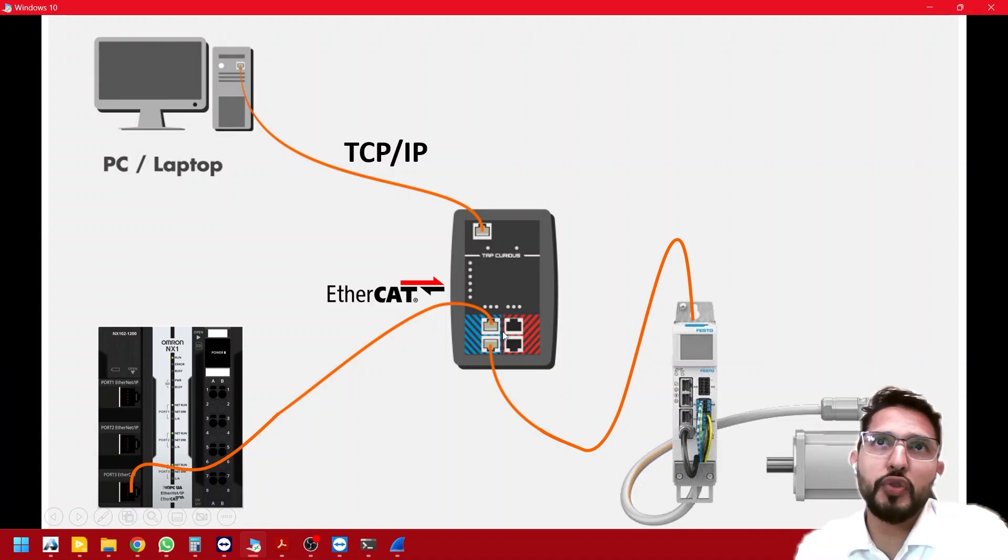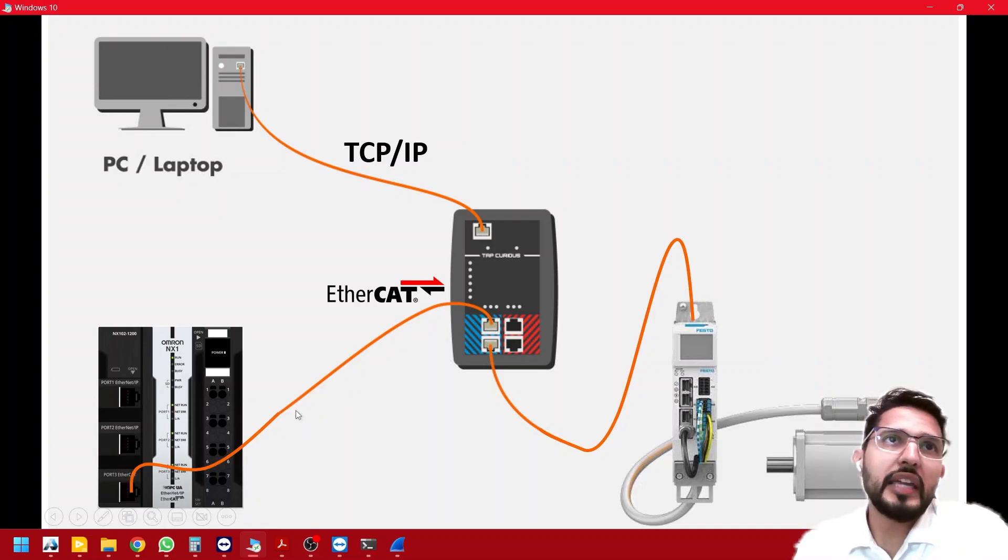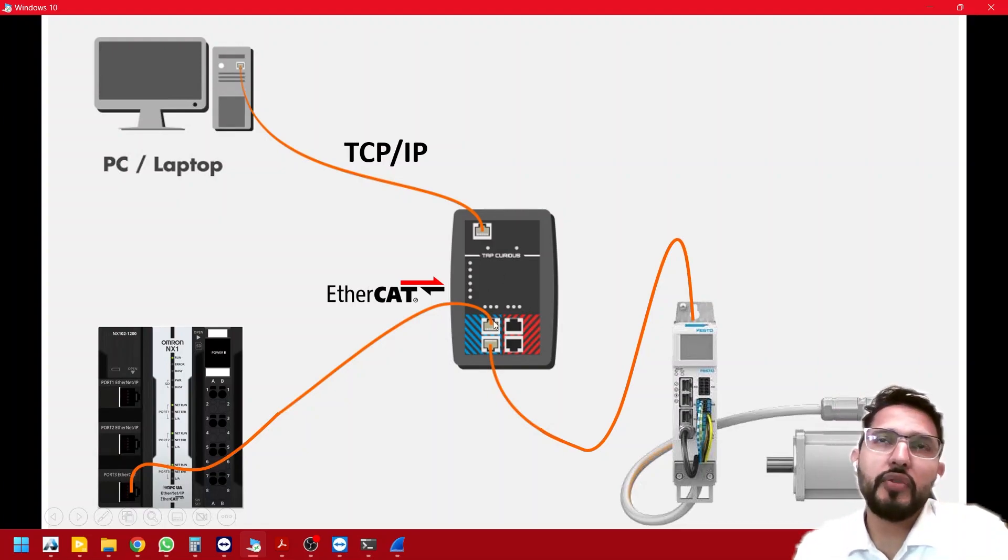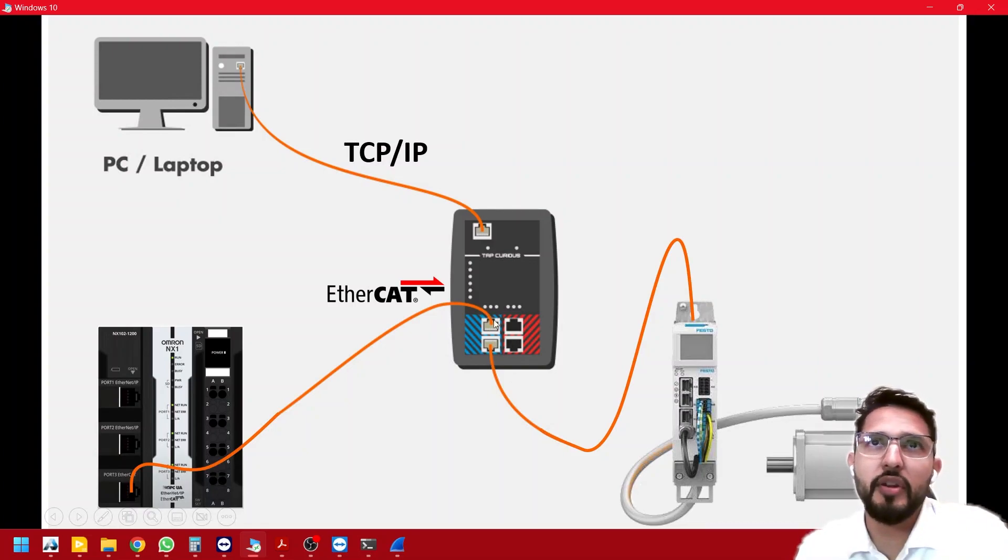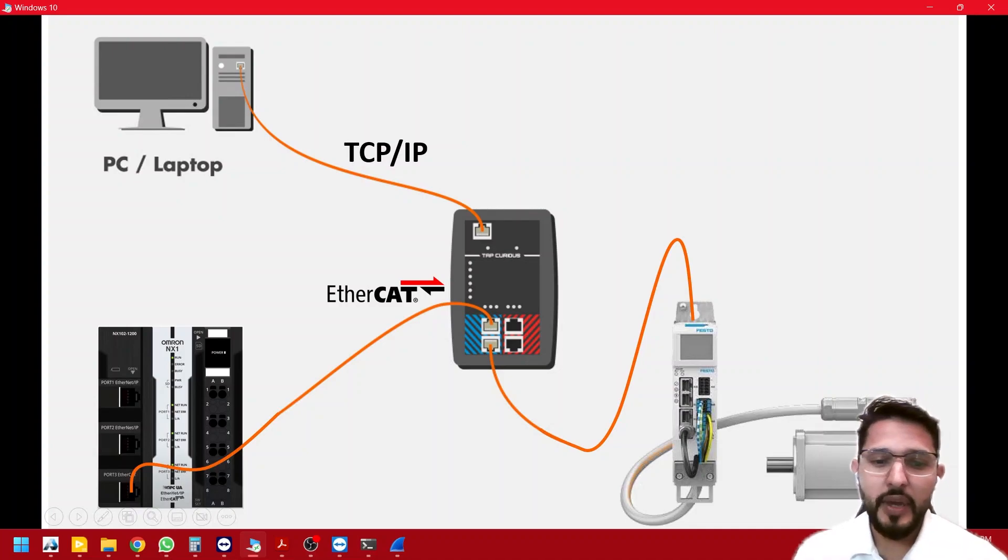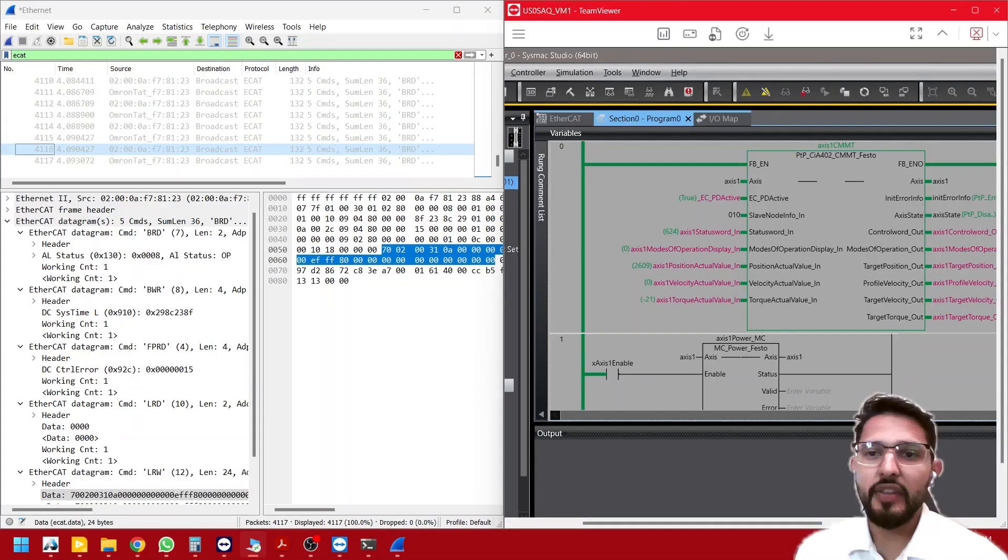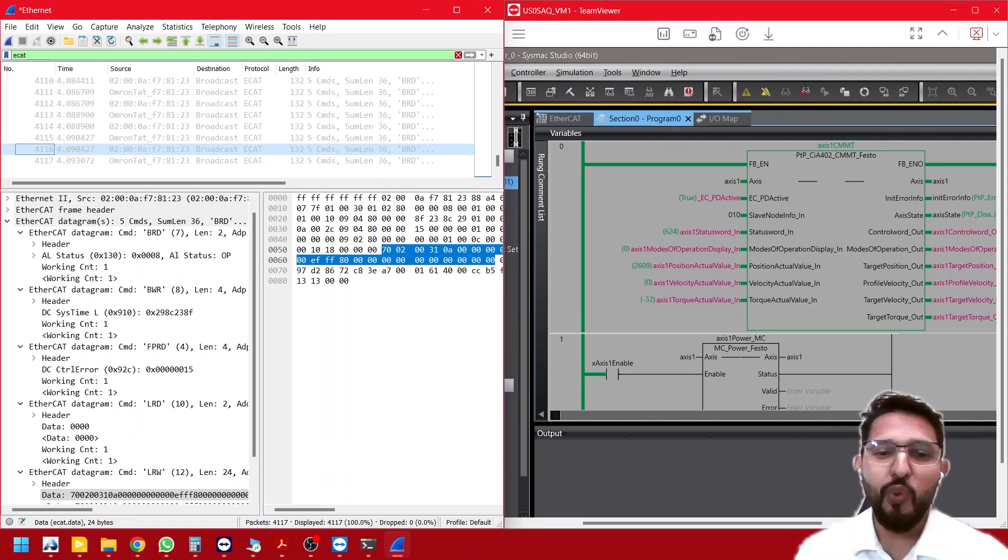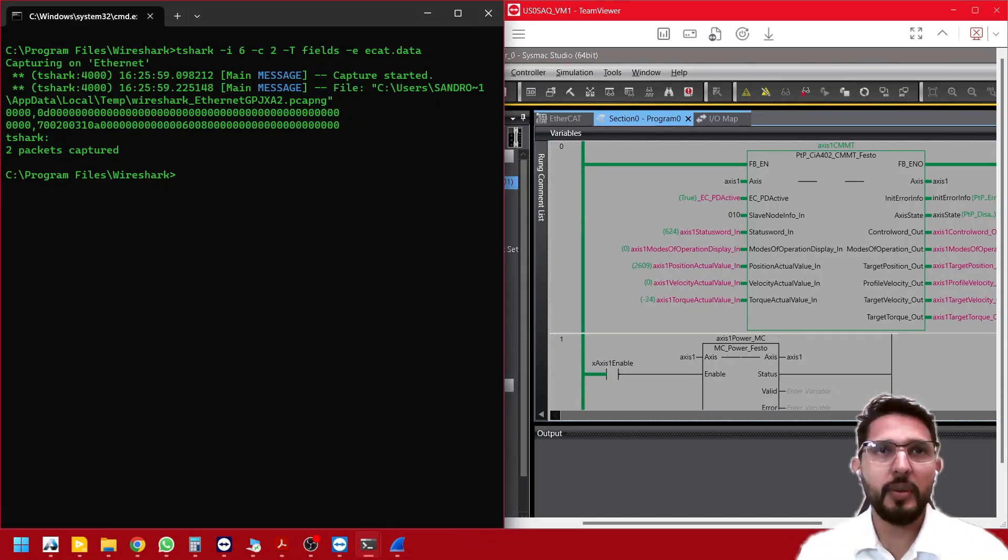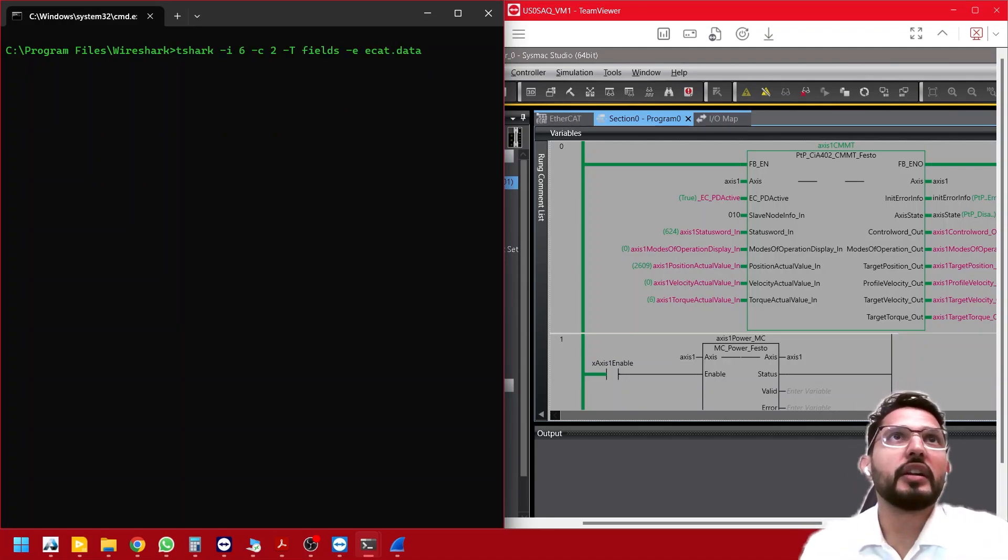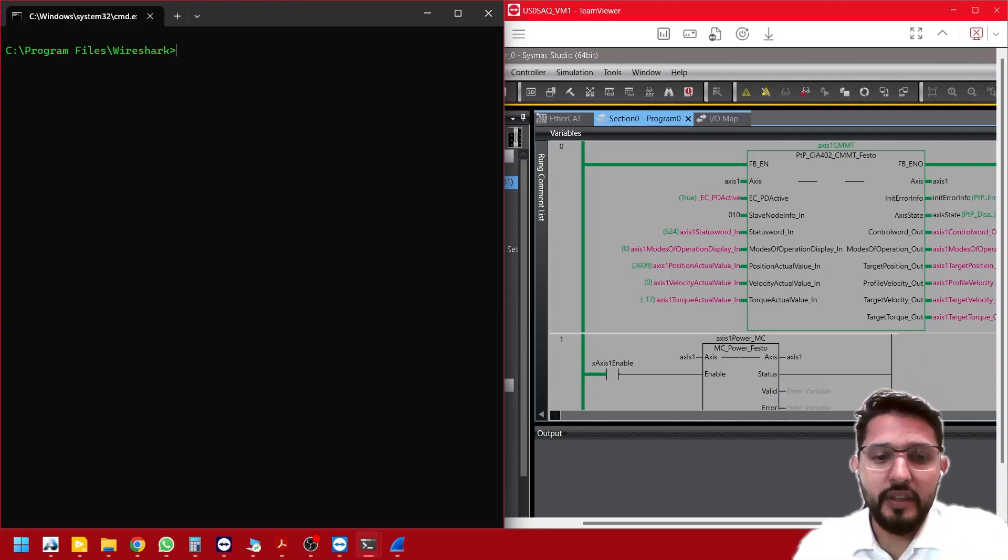It's almost no latency. I believe on the website from Kunbus, they say that there's zero latency, so there's no delay. Basically, it just intercepts the data that's coming over some sort of Ethernet communication from this port to this other port. In the actual application, this PLC here on the left, the Omron PLC, is connected directly to the Festo servo drive. What we're doing for the purpose of this analysis is we're intercepting the telegram or the communication and analyzing it here. I'm going to use two pieces of software mainly: one of them is going to be Wireshark, and the other one is going to be the Sysmac Studio from Omron. At one point, I'm also going to utilize the command prompt using T-Shark from Wireshark.